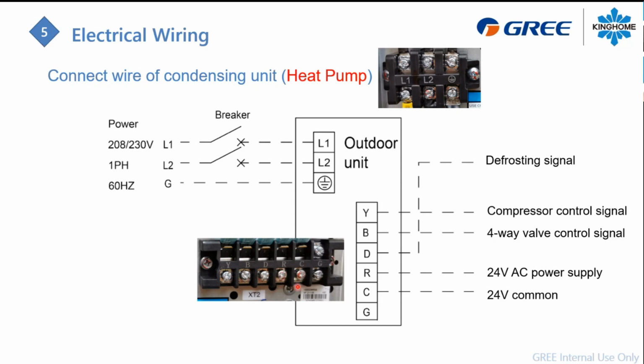R and C is your power for the 24-volt connection. So R, it's always your power. C, it's the common. And the G terminal right here, it's not in use. So there's no connection into it. It's just laid there. There's nothing to do with the G connection.